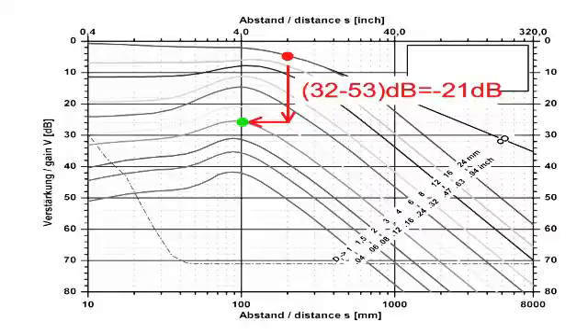On the diagram, the final position found in this manner allows us to determine the diameter of the equivalent reflector size. In this example, the final position rests on the 3 mm equivalent reflector size curve, indicating that the discontinuity has the equivalent reflectance of a 3 mm diameter flat bottom hole.